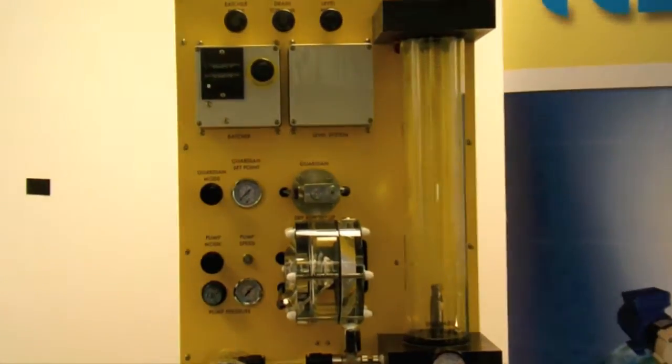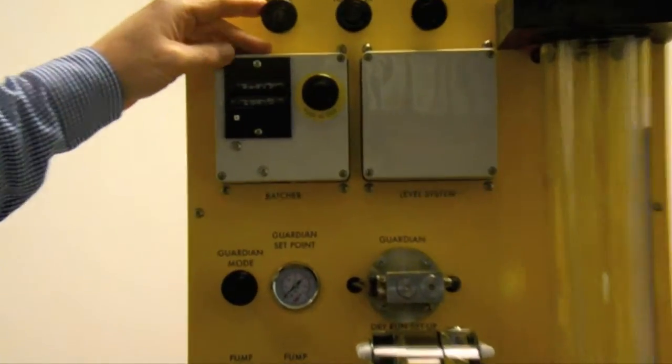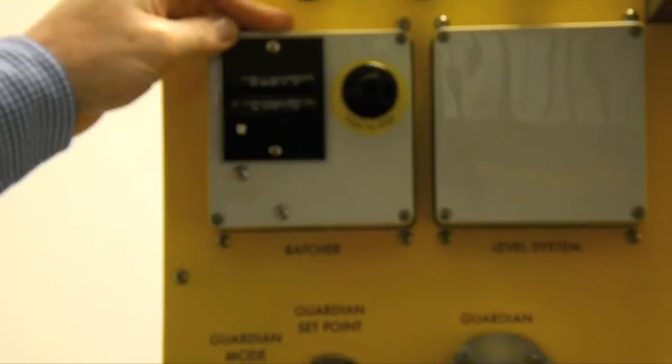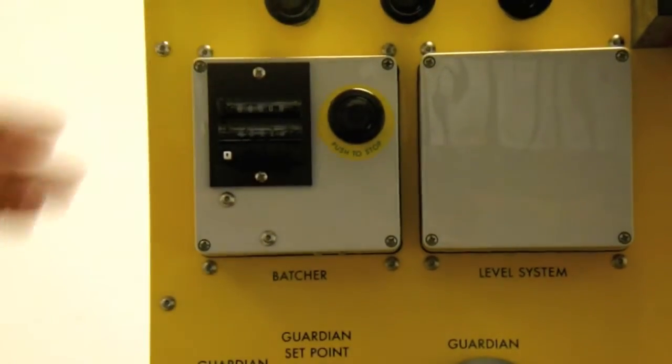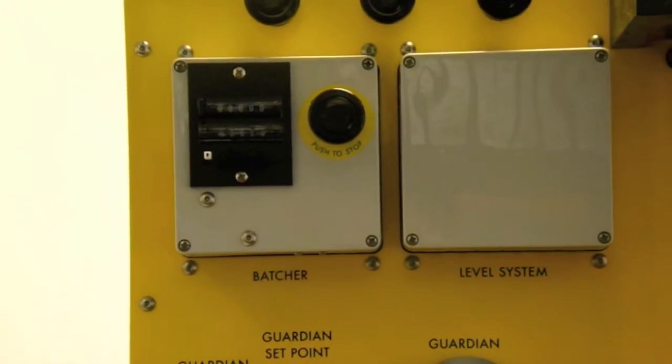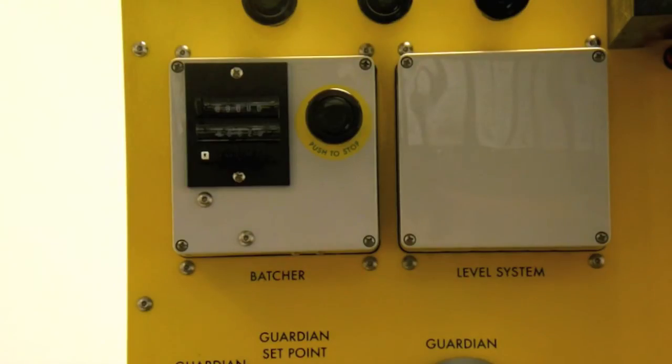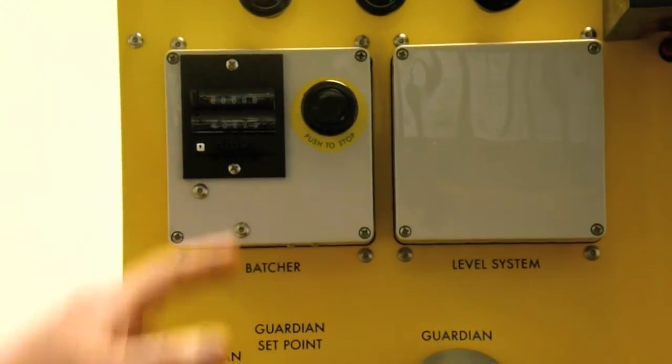The next system I am going to show you is our batcher. The batcher is very useful if you have to pump predetermined volumes. So let's say you needed to fill 10 containers with 10 litres in each one. What we do is because we know the pump volume per stroke we just simply work out the number of strokes that we need to do. So let's say this pump does half a litre. We want 10 litres so we put in 20 strokes on our bottom counter here.